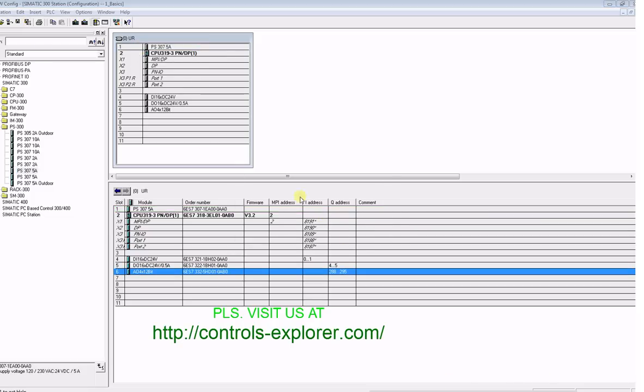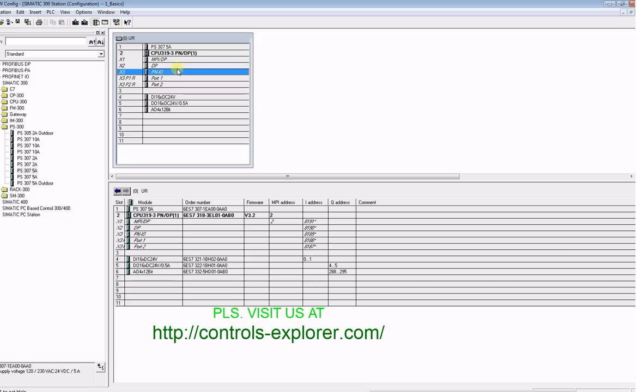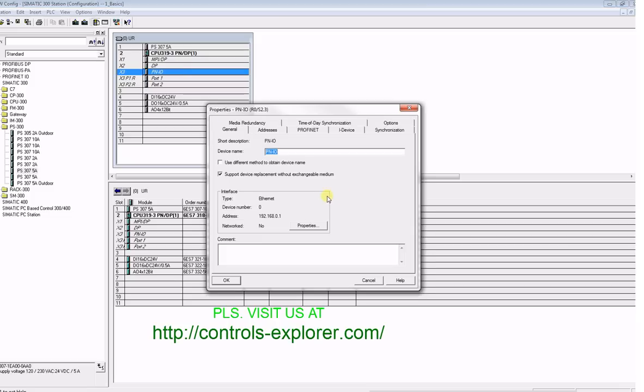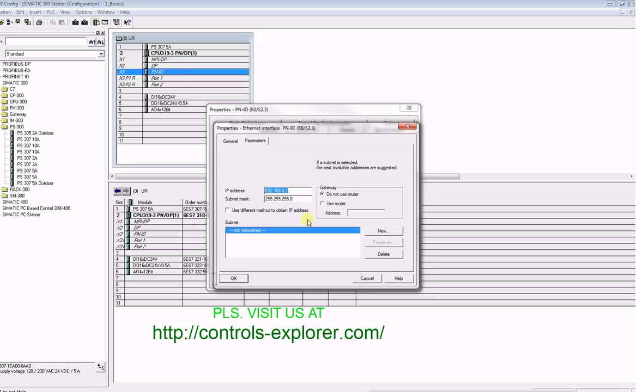Next, let's create the PROFINET network. Double-click the PN I/O and you could see here under properties the IP address. First of all, if you have to change it, you can change it from here. For this example, we are good with 1.1. The most important thing here is the subnet, so hit new on the right side.